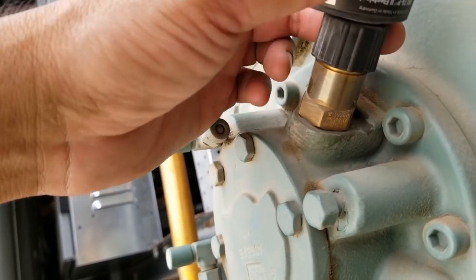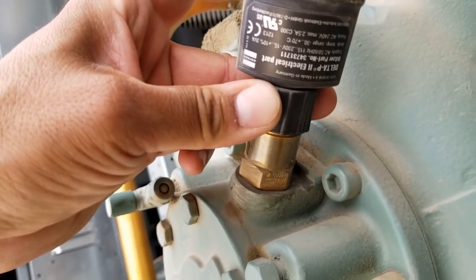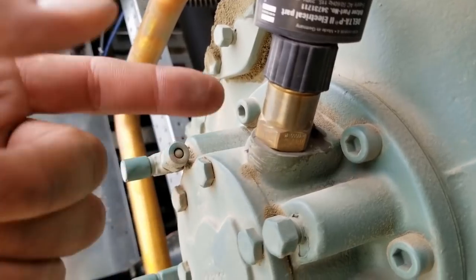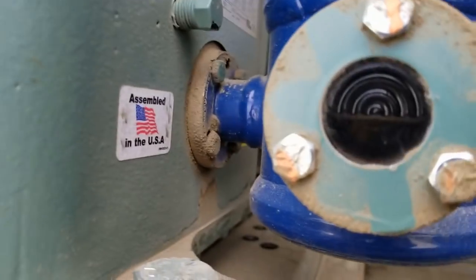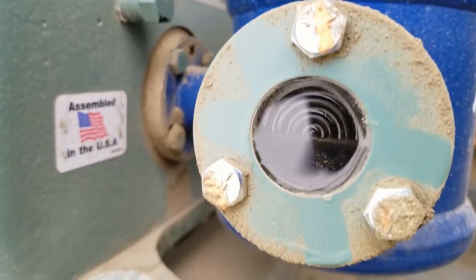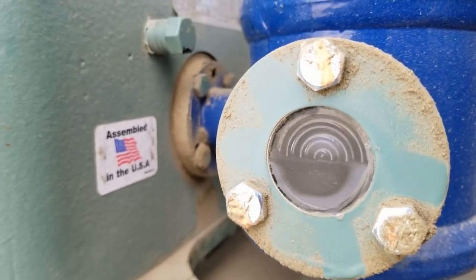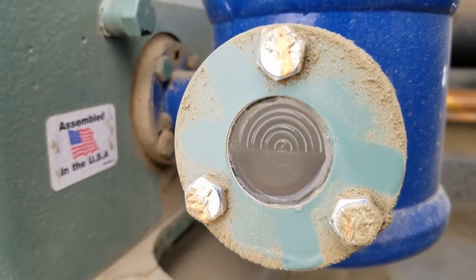So we're gonna take this off right now and see how the screen is. Because if you can see right here, the oil is pretty dirty. So I'm assuming my screen is probably dirty, which is causing my compressor to go off on oil fail. Let's check that out.